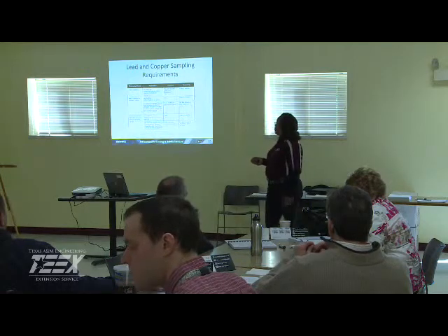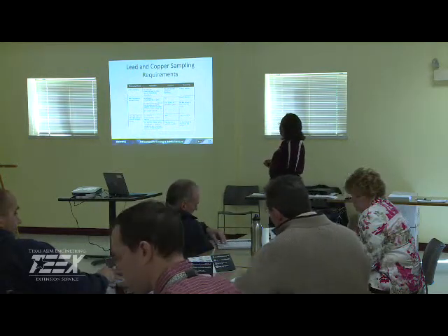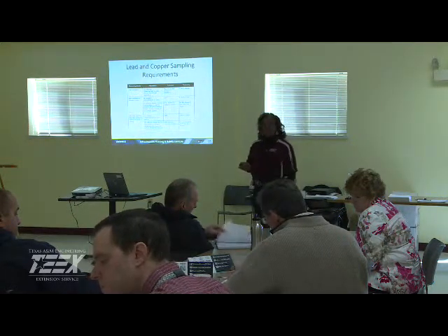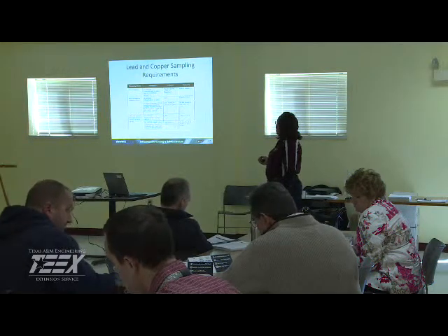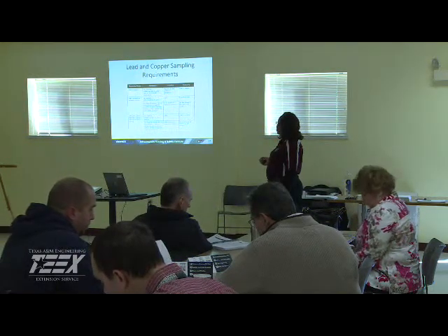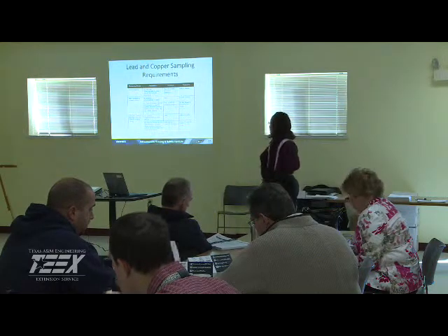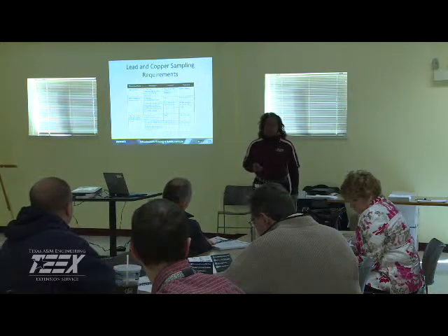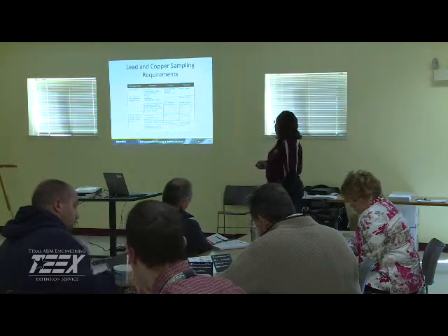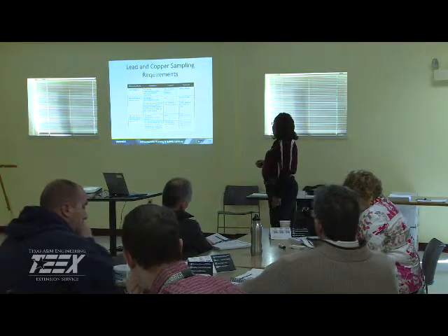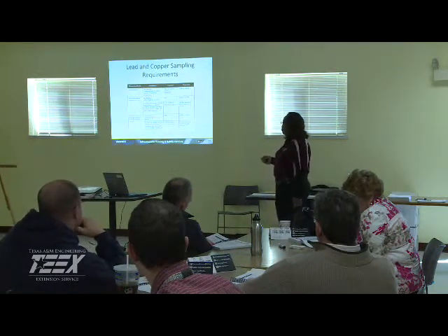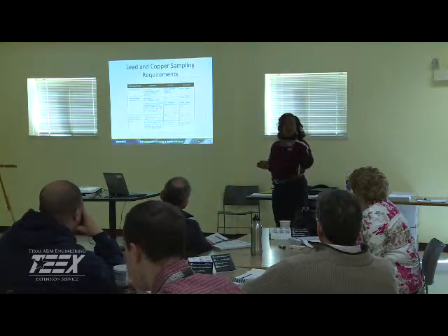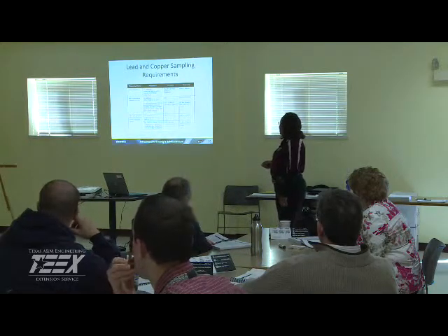For lead and copper samples, you have this table in your book also. For the initial monitoring period, we're looking at all those parameters that we just recently mentioned, and the location should be taps and at the entry points to the distribution system, and we're going to do it every 6 months. If we have a hit or a hot spot, you're going to increase that monitoring frequency also. And I think I have a quick reference guide to lay that out in a minute here.